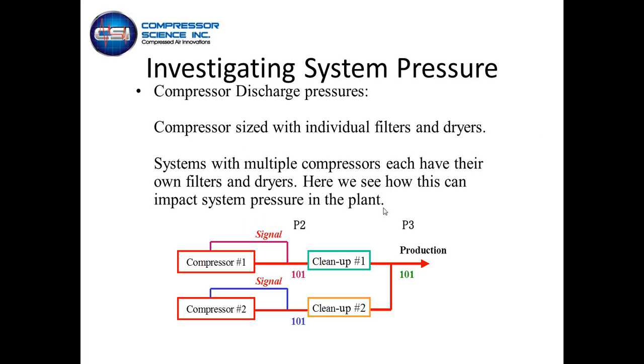So we don't really have a common pressure signal downstream that's actually loading and unloading the compressors. You've got individual compressor controls that are trying to fight across restrictions in the piping or the cleanup treatment equipment in order to satiate that demand out in the plant.